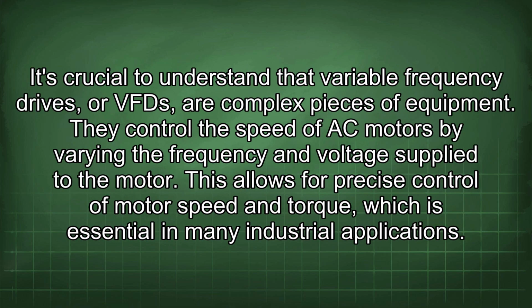It's crucial to understand that variable frequency drives, or VFDs, are complex pieces of equipment. They control the speed of AC motors by varying the frequency and voltage supplied to the motor. This allows for precise control of motor speed and torque, which is essential in many industrial applications.